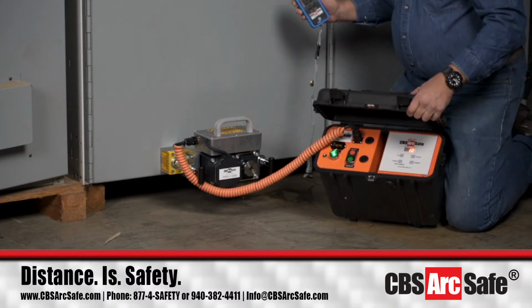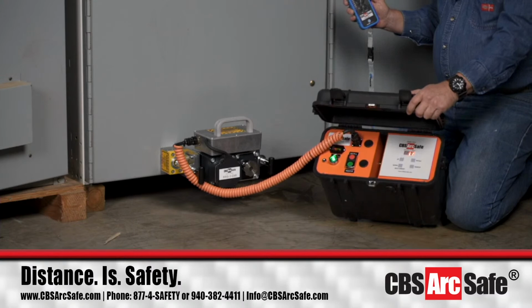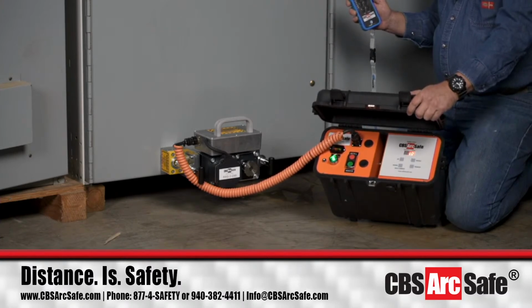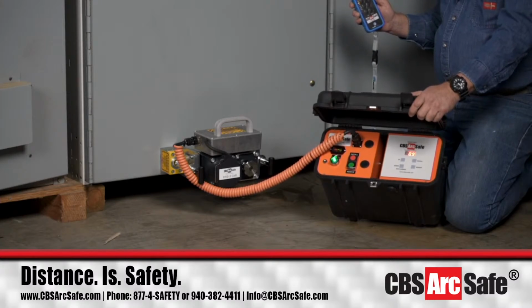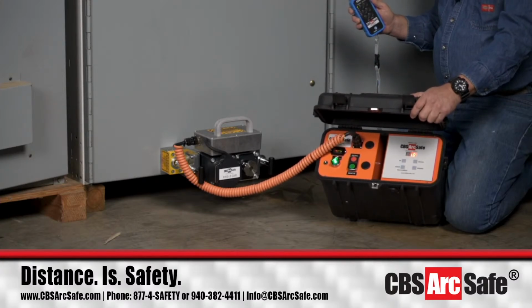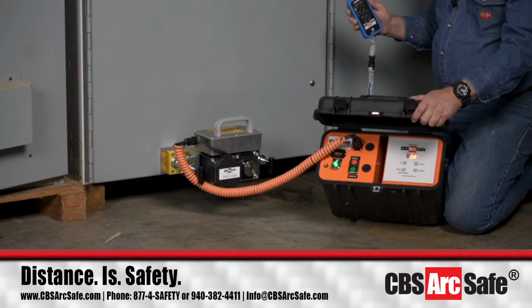Now, just remember, I mentioned Siemens has the 3AF for their other medium voltage breakers here we find domestically. It's an older limited edition, what I'll say. But you can also find these breakers, believe it or not, manufactured and licensed by Hyundai in the Middle East. Instead of it saying 3AH, it'll have a slightly different designation on the start of it. You're going to go, wait a minute, that looks exactly like a Siemens breaker I'd find in America, but that says Hyundai on it. Well, it's because it's made under license.